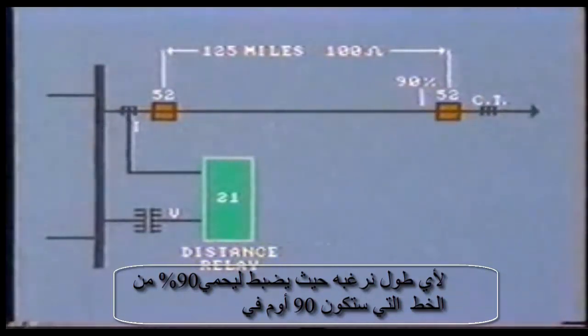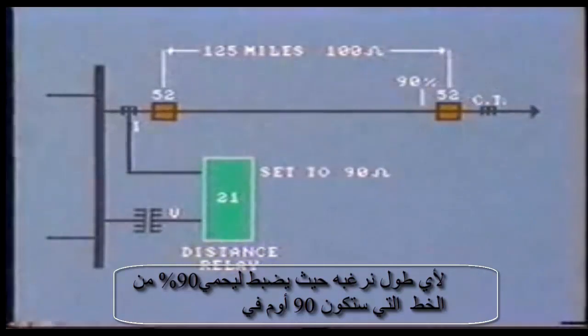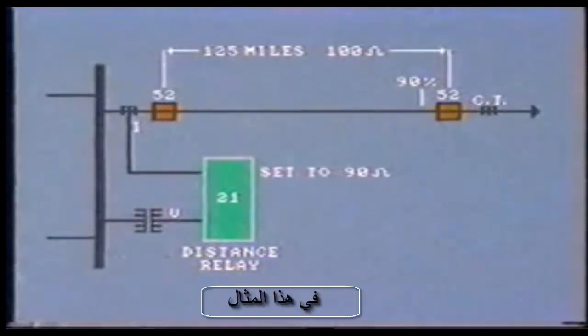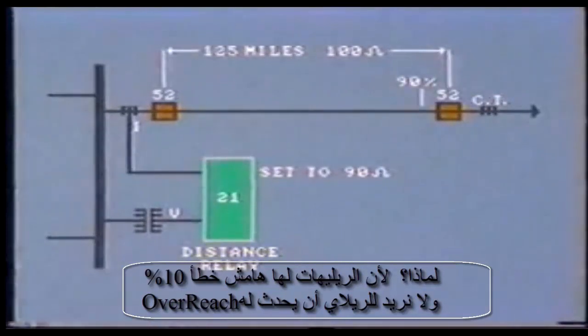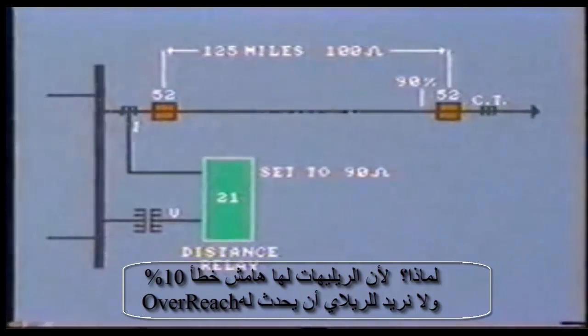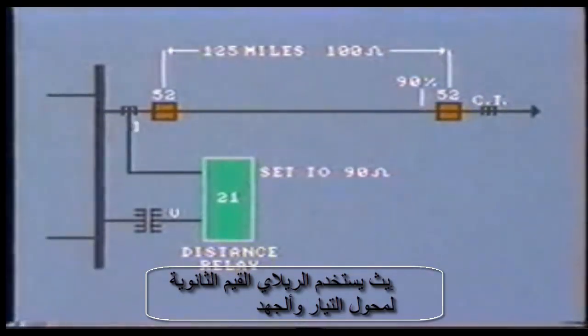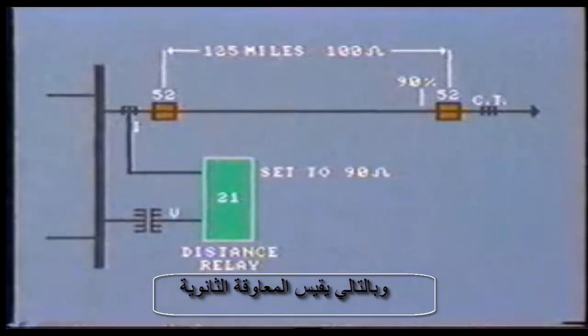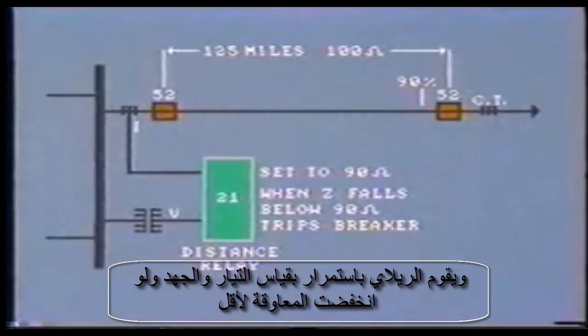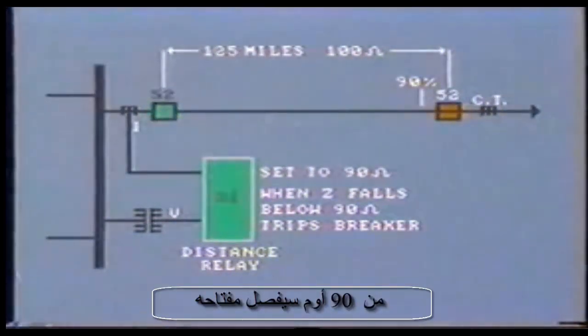Typically, it will be set to protect up to 90% of the length of the line — that is, for an impedance of 90 ohms in this example. Relays have a 10% error margin, and we don't want the relay to overreach. The relay is using secondary values from the CTs and VTs, so it really measures secondary impedance. The relay continuously compares voltage and current, and if the secondary impedance falls below 90 ohms, it will trip its associated breaker.